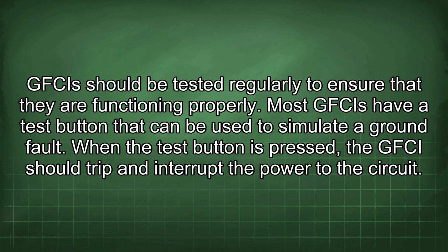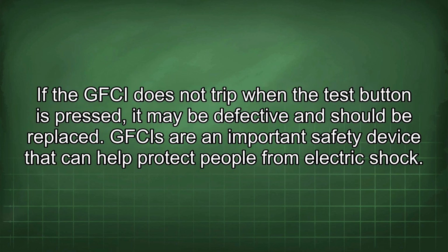GFCIs should be tested regularly to ensure that they are functioning properly. Most GFCIs have a test button that can be used to simulate a ground fault. When the test button is pressed, the GFCI should trip and interrupt the power to the circuit. If the GFCI does not trip when the test button is pressed, it may be defective and should be replaced.